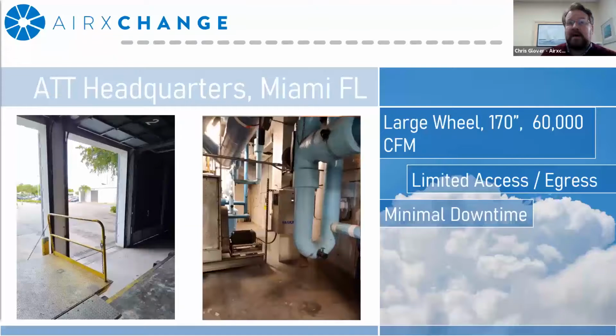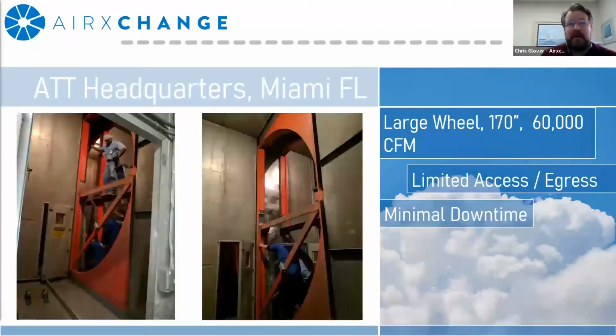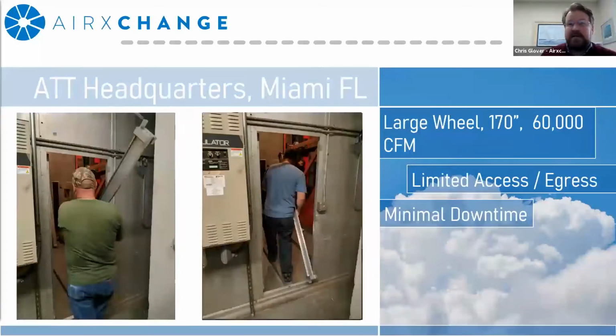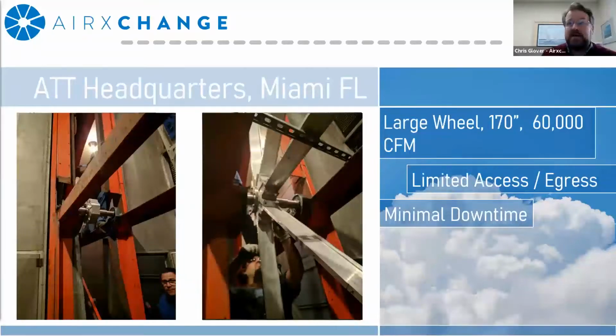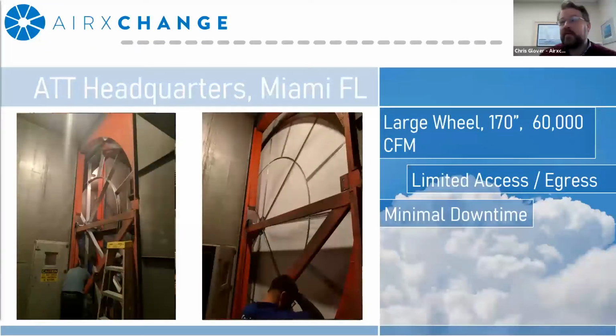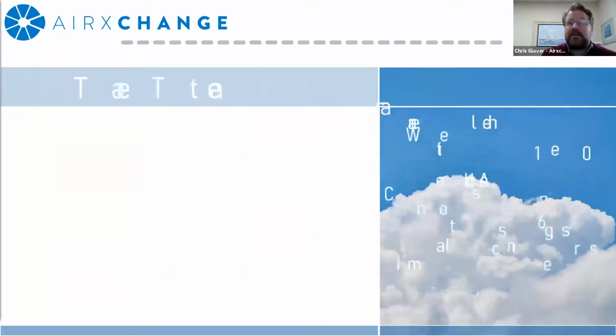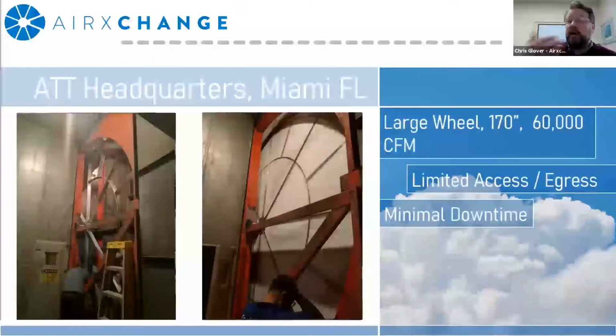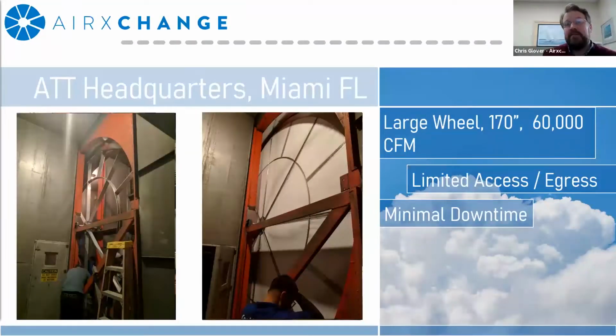Once again, it had to be done while people weren't present inside the building. So we had to complete it over a weekend's time. So the contractor essentially came in, removed the old wheel. We provided a kit based upon the existing site-related wheel. And the entire project was able to be completed during 1 weekend's worth of time. So they started it on Saturday and they finished it on Sunday. And the benefit here is now when the unit gets to be dirty like it was in the original wheel, now the maintenance folks, the service folks can go in and take the segments out, wash them, clean them over time to help keep this device operating for a very, very long time.